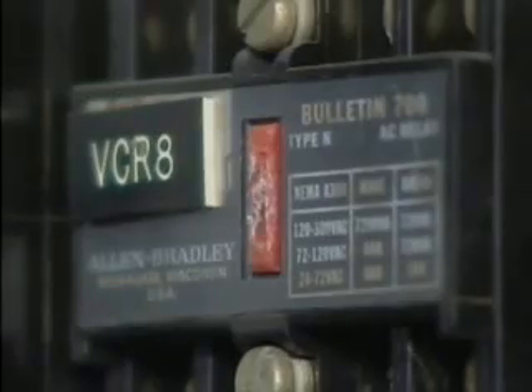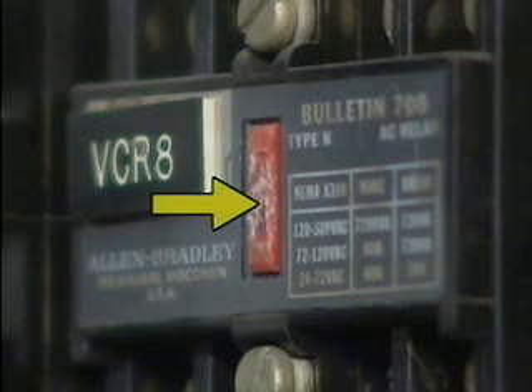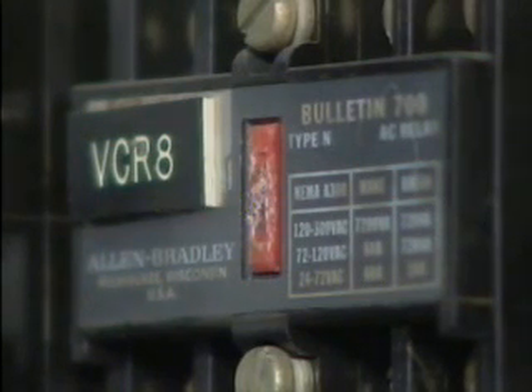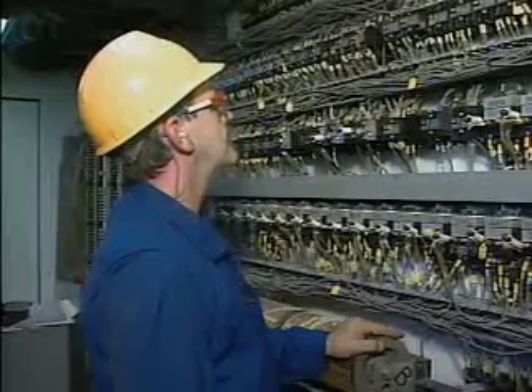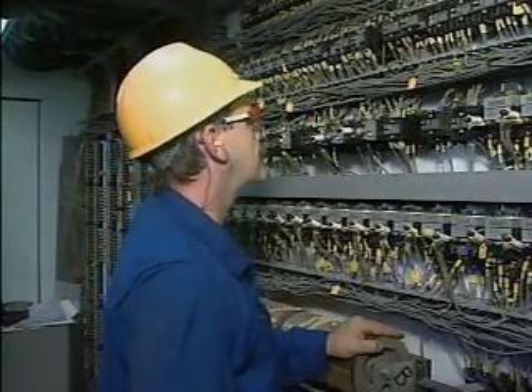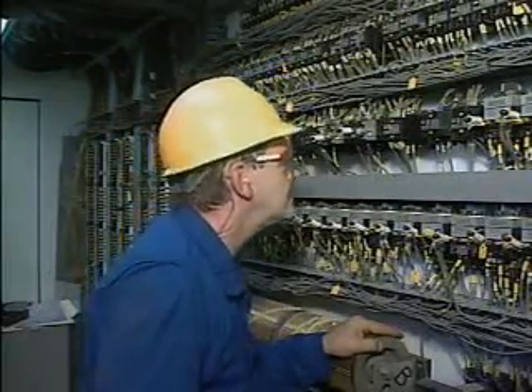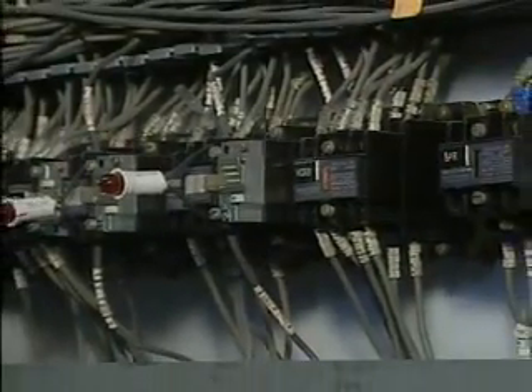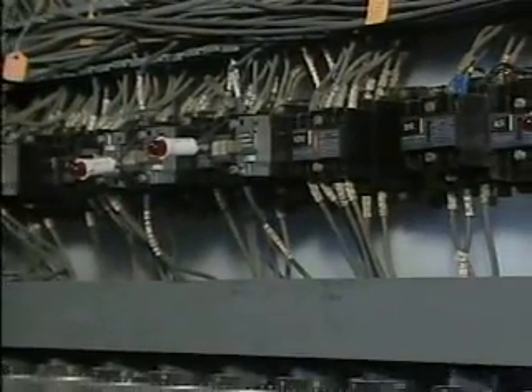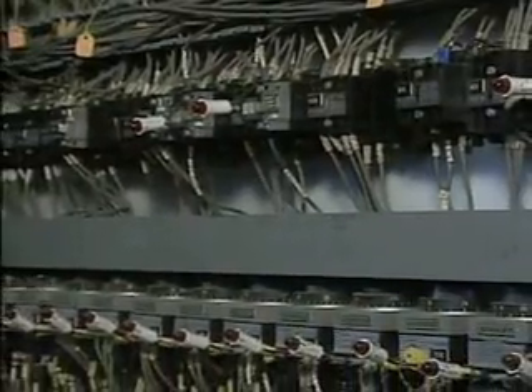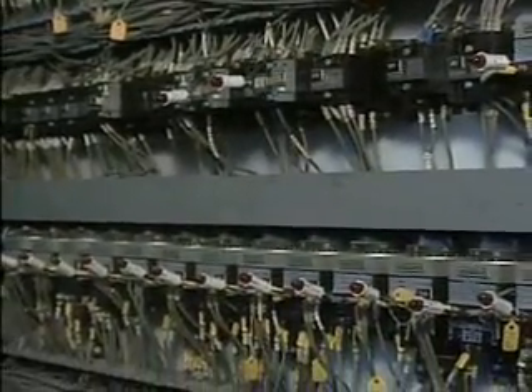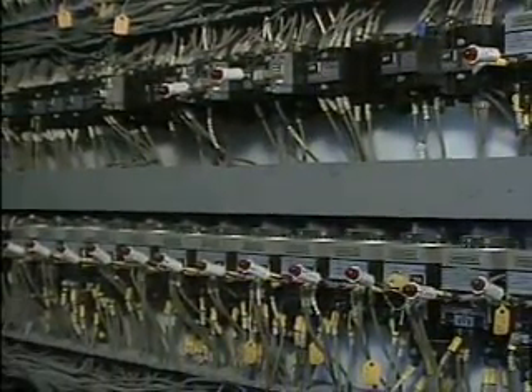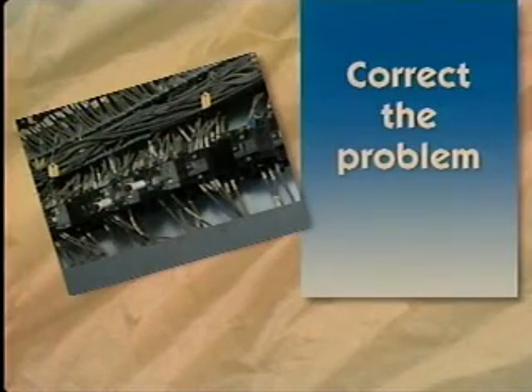During his visual inspection, he sees that the relay's indicator bar or target is not pulled in. This indicates that the relay is not energized. He also notices that there is a loose wire on one side of the relay's coil. Given the relay's location in the plant, it's very likely that vibration caused the wire to become loose, probably during the extended period of time that the relay was not being used. Now that the electrician has determined the cause of the second problem, he must correct it.